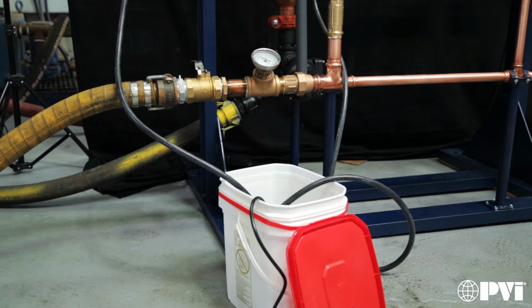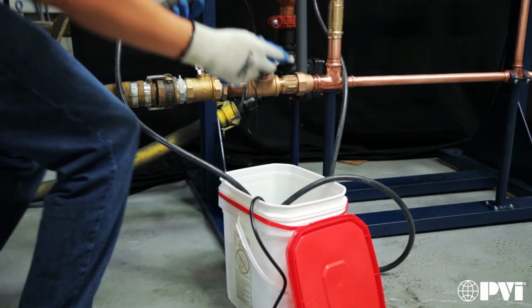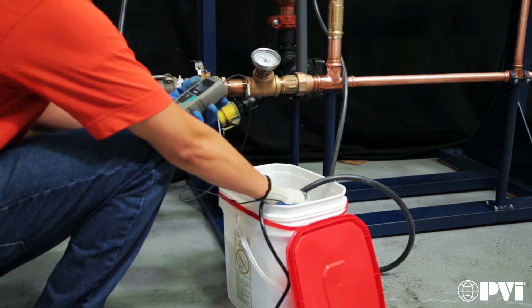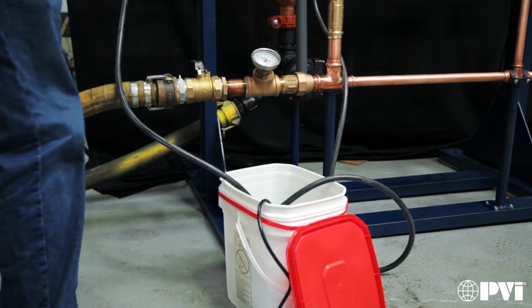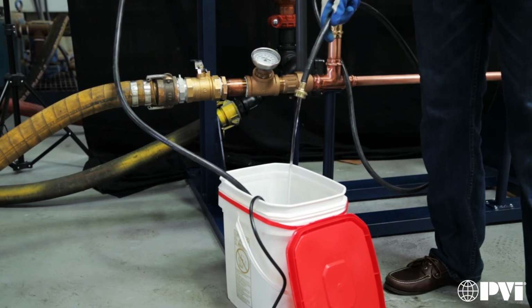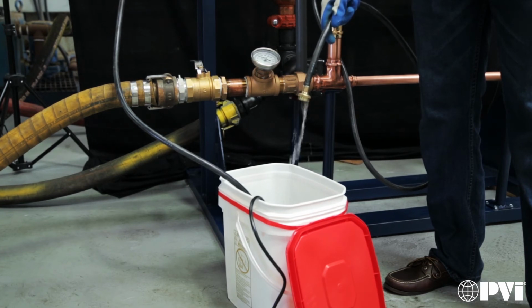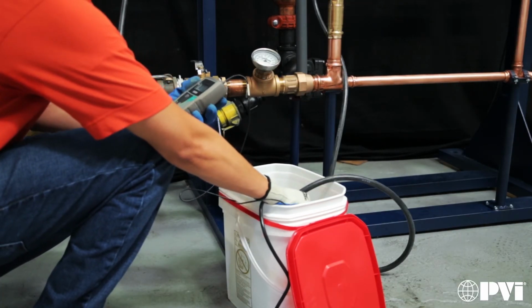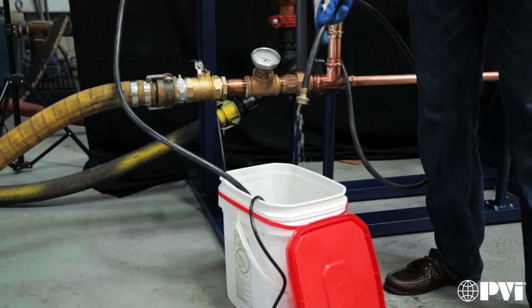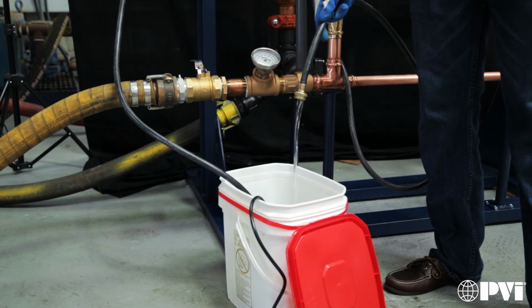surfaces. Turn on the pump to begin flow into the top of the heat exchanger, with residue falling into the bucket. Let the cleaning process run for a minimum of 30 minutes. Then turn off the pump and test the pH of the solution. The solution will approach neutral at 7.0 when large amounts of scale are dissolved. When the solution approaches neutral, replace the solution and return to the cleaning process. Continue the cleaning process until the pH level of the acid remains consistent. After flushing, fill the bucket with fresh, clean water and flush the heat exchanger and plumbing excessively. Replace water and repeat. Return the plugs to the clean-in-place fittings and secure.